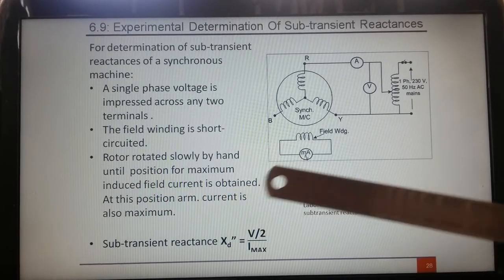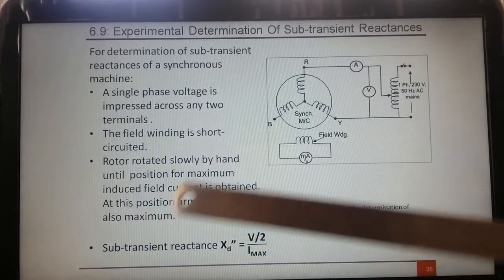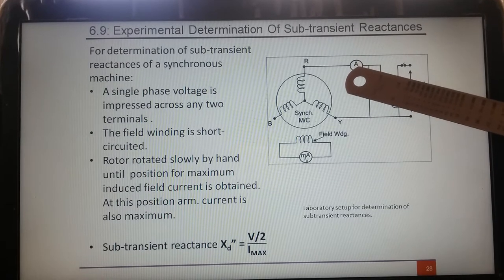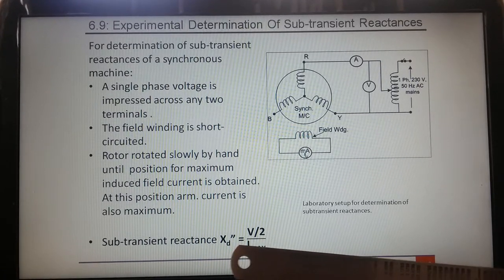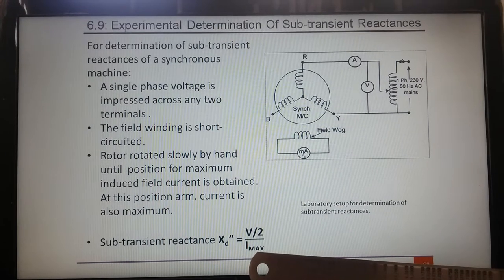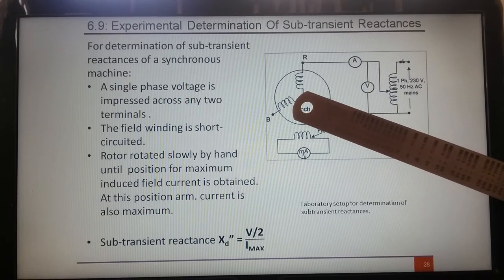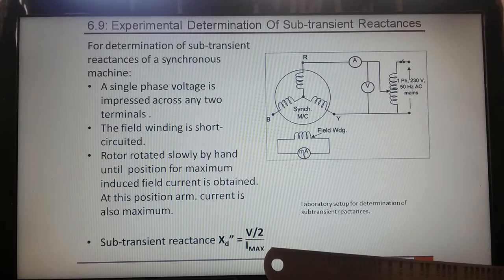The rotor is rotated slowly by hand until the position for maximum induced field current is obtained. At this position, the armature current is also maximum. You record this reading — that particular value is maximum — and at that point the machine is at the D-axis, because both the field part and the armature part of the winding along the D-axis have minimum air gap, which is why the current is maximum at that time.